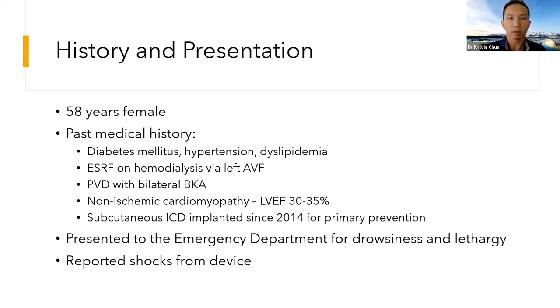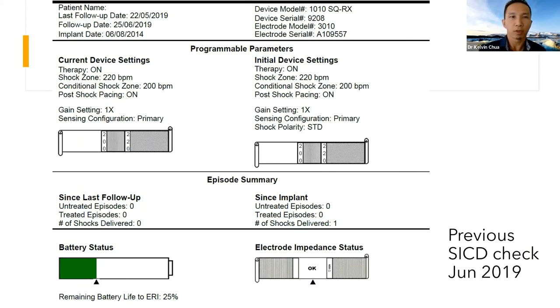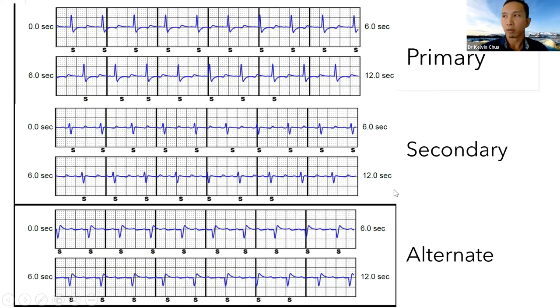So she reported shocks from the device. I'll quickly move on to some of the device tracings. This is a previous SICD check done a month before her current admission. You can see this is a 1010 device, a first generation SICD, with a conditional zone programmed at 200 and shock zone at 220. The 1010 device does not have SMART Pass available, and you can see one lifetime shock delivered, corresponding to the time of implant when defibrillation testing was performed.